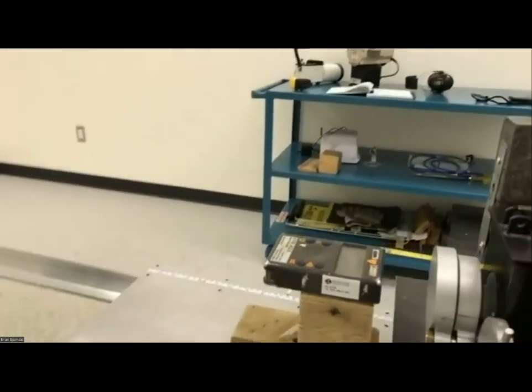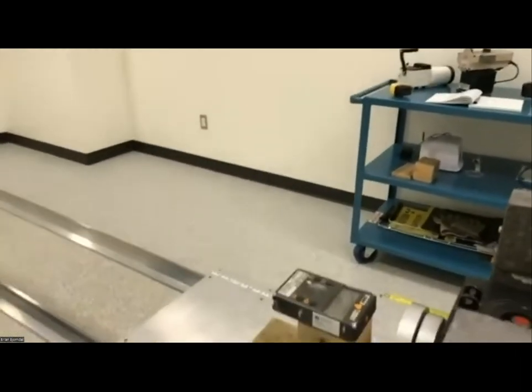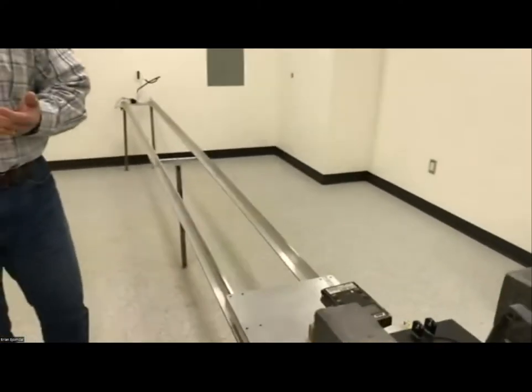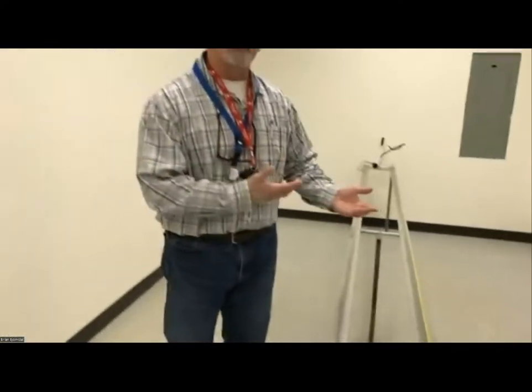The nice thing about the one we have is that with these attenuators, it allows us to quickly vary the intensity of the field without having to physically move the instrument. Now, we could easily leave the attenuators off and adjust the instrument, but this makes it easy and efficient for doing instrument calibrations. So no matter what type of instrument we have, as long as it's suitable for gamma measurement, we can do the same process.